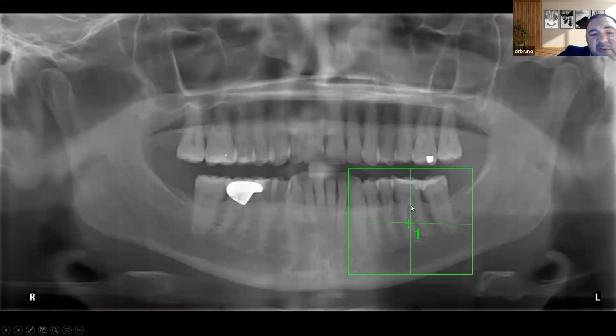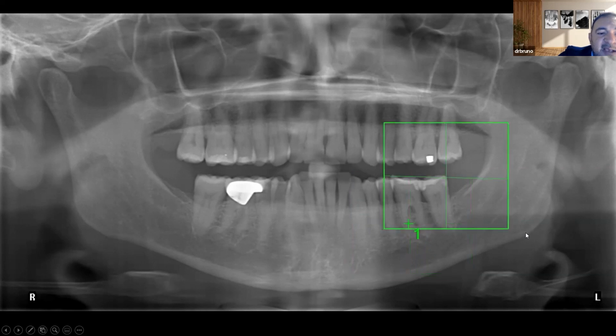The reason you want to place the chin rest on position 1 is to acquire a smaller field of view, or even a medium field of view of the mandible, without the maxilla interfering. But if you want to scan the maxilla on position 1, the vast majority of times what's going to happen is this: as you move this up, this is going to turn red.